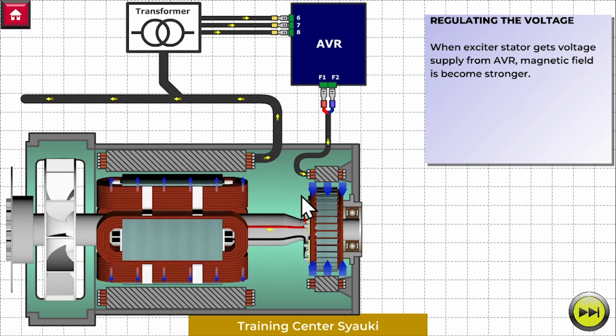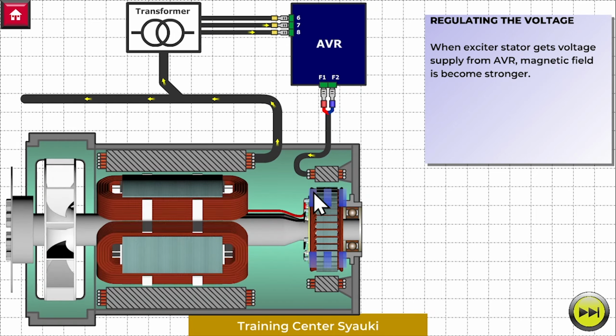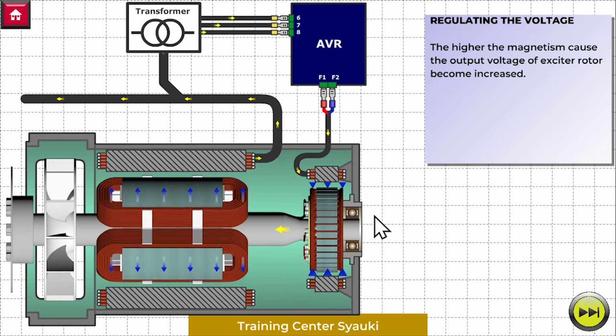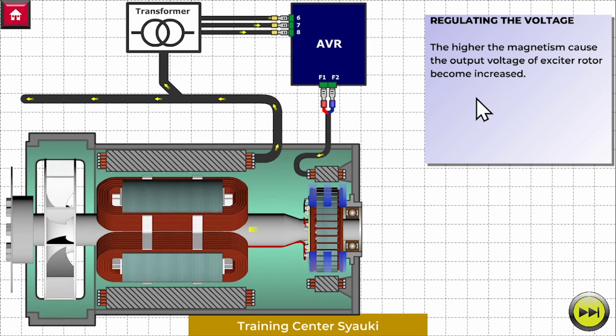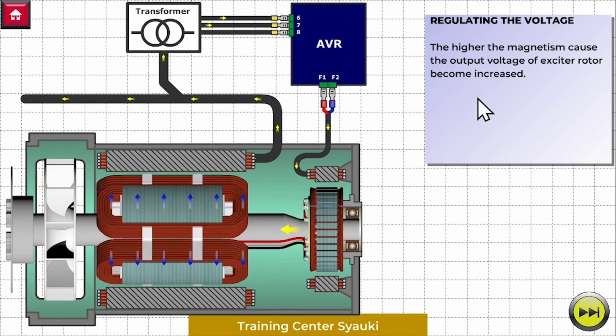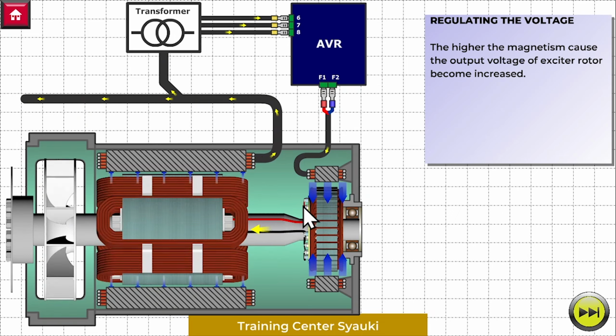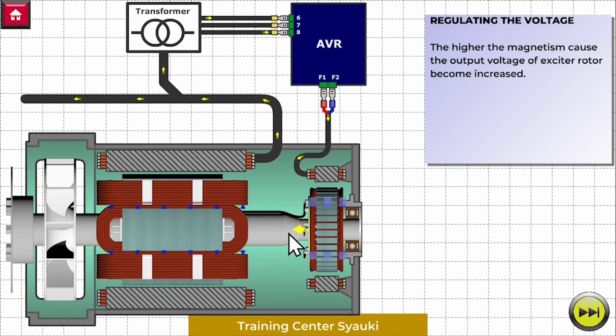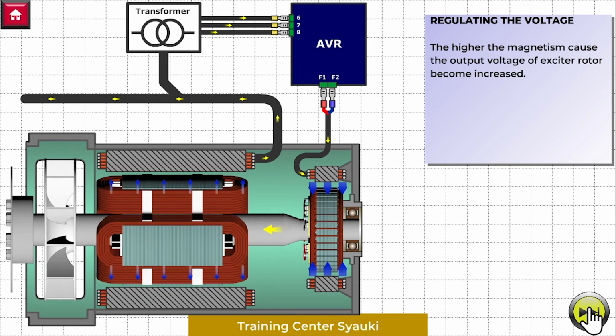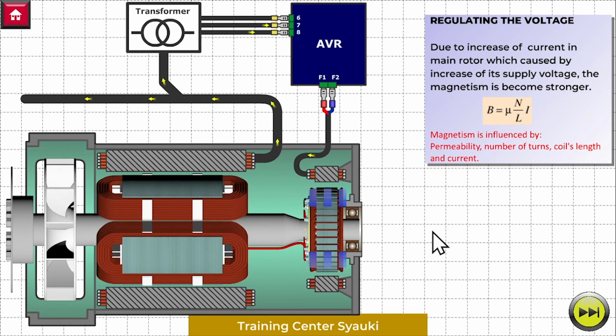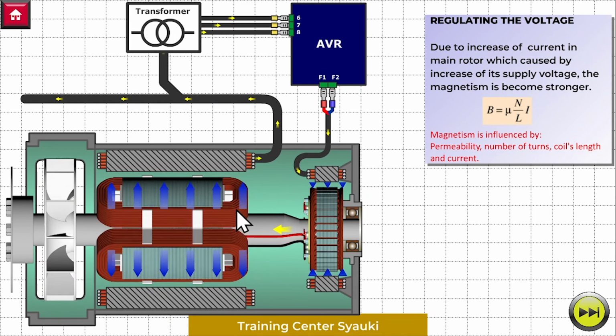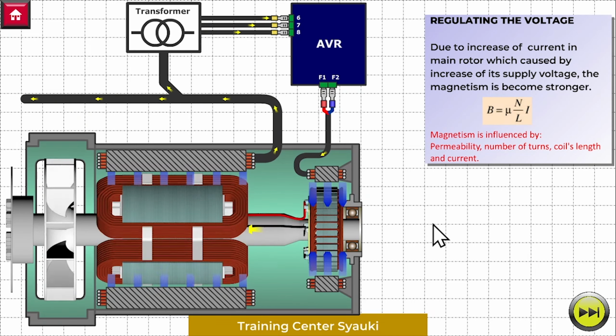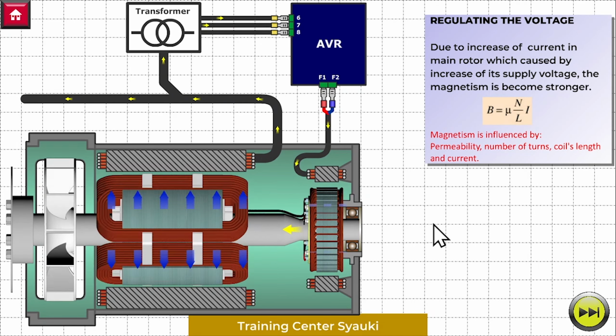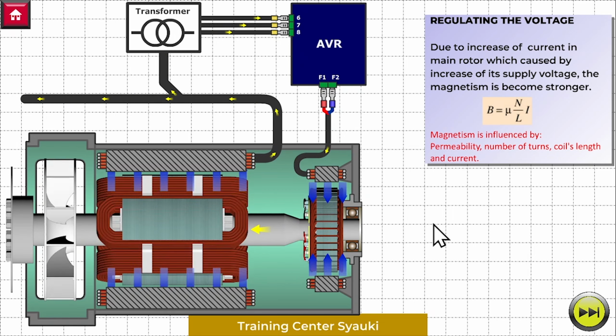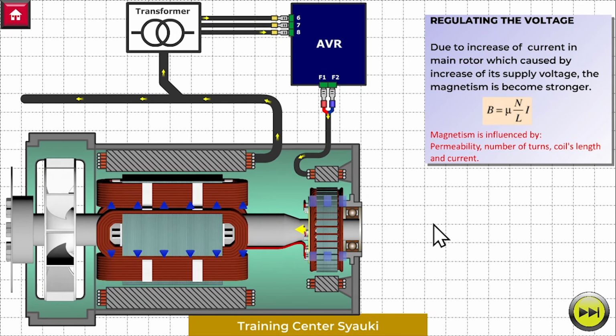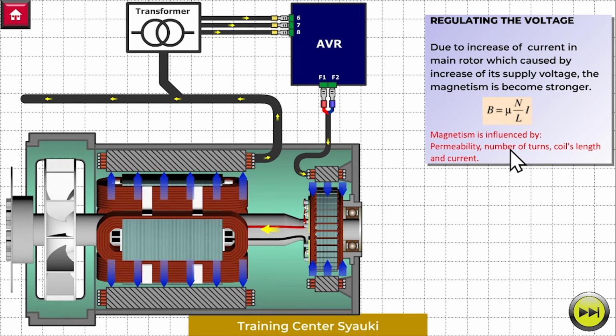What is the effect of the magnetic field becoming stronger? The effect is that the higher magnetism causes the output voltage of the exciter rotor to increase. Due to the increase of current in the main rotor, caused by increase of its supply voltage, the magnetism becomes stronger.